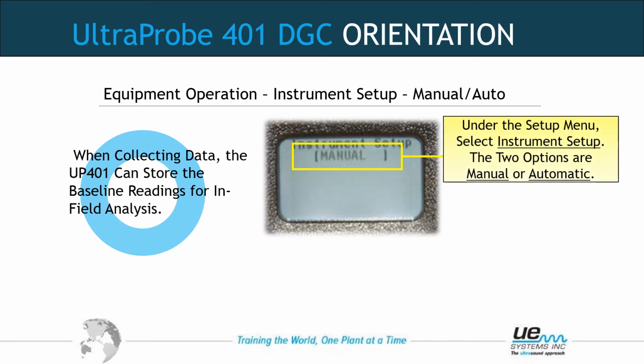Instrument setup is fairly important if we're route-based. While baselining, we don't want the instrument to read any information because there is no information to read, and it will default to all of its values per test point. So it will keep defaulting every time you store a record back to 30 and 70. The sensitivity will go all the way up, no frequency change, anything. We don't want that while we're baselining.